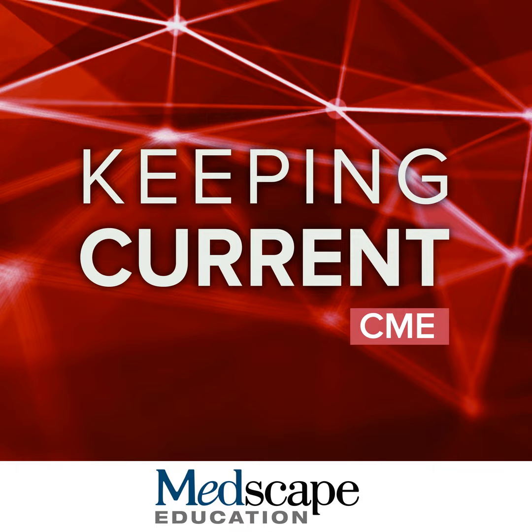There are different regulatory pathways. There's a wellness app versus software as medical device. So when you want a digital therapeutic, you really have regulatory oversight. If not, then it's a wellness app. You need enforcement discretion. There needs to be a different either 510(k) submission, which is you're applying something to a treatment that's already out there, or it's a de novo pathway. But it's good that we have now regulation, which also means there's reimbursement possible for digital prescription therapeutics.